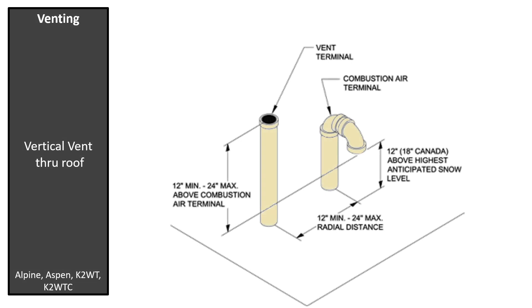If we choose two pipes through the roof, the vent pipe must be 12 inches to 24 inches above the air inlet terminal. The opening of the vent should be vertical with no elbows or any other fittings installed. There is no concern of rain and snow entering the vent termination. The air intake must be 12 inches to 24 inches away from the vent and use two 90-degree elbows to terminate the air intake down to avoid getting rain into the intake termination. The termination of the air intake must be a minimum of 12 inches above the anticipated snow level.